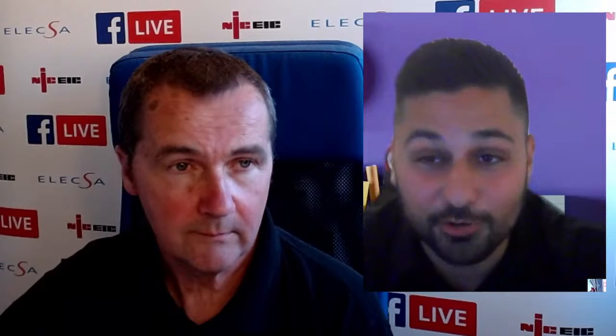So to answer your question, the answer is no. You don't, because it's existing, and more than likely it would have been installed at a time when it was compliant. So it's not something that would need to be upgraded. And we have Best Practice Guide 4. For those doing EICRs on a regular basis, Best Practice Guide 4, I would say, is our mother in the electrical industry for EICRs at the moment, and what we follow. It's the industry standard for EICRs, and it's quite important to be familiar with it, because it does cover you. On that guide, Sam, it does state, like what we're talking about now, that it doesn't warrant a code - it's an item worthy of a note, but does not necessarily warrant a classification code. So it's always good practice to detail on the comments of the existing installation and things like that.